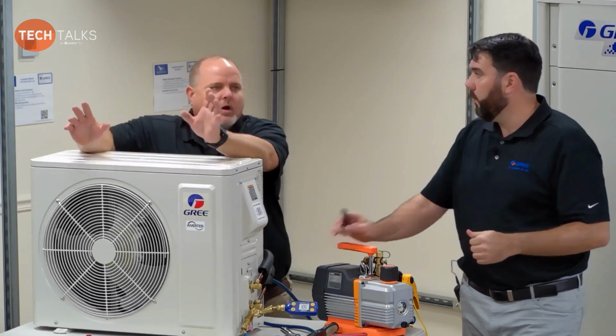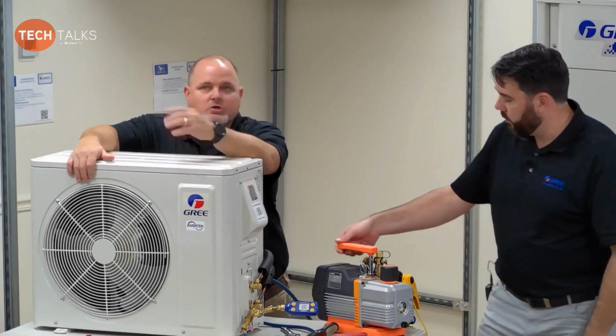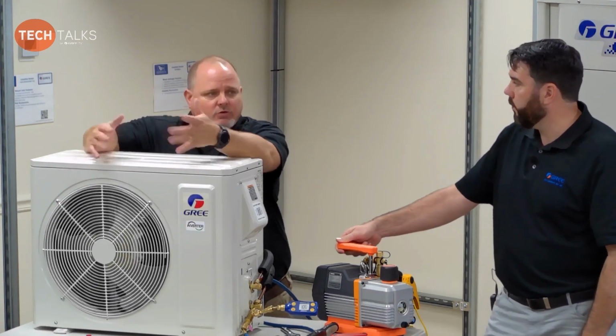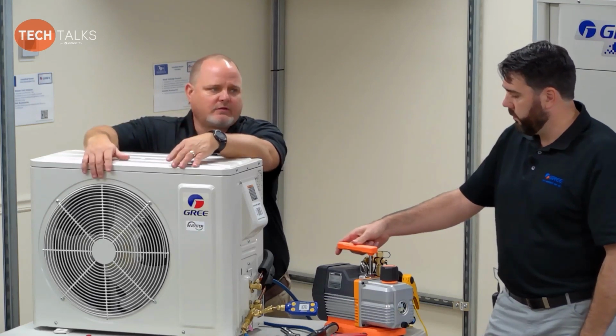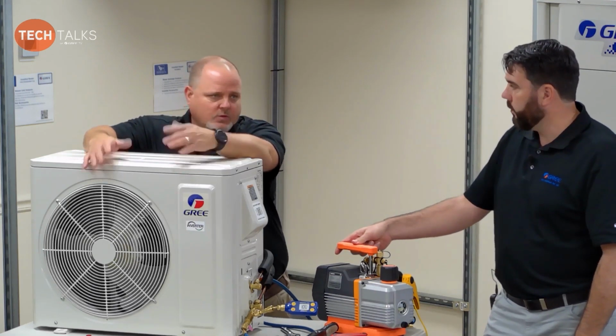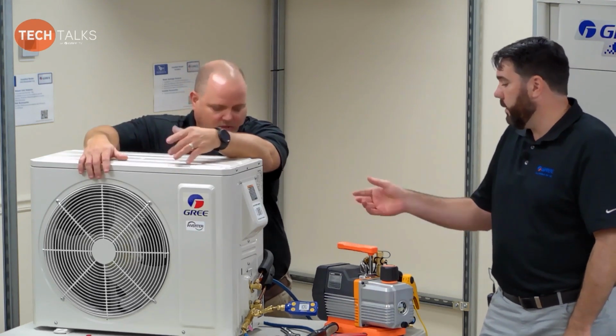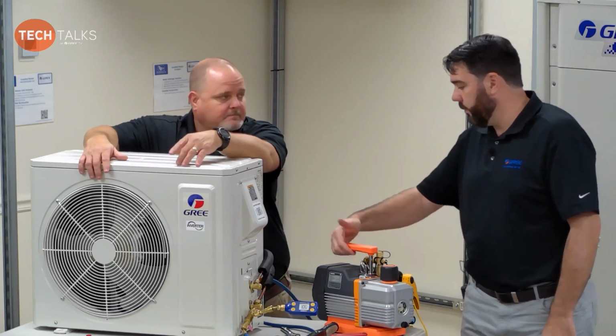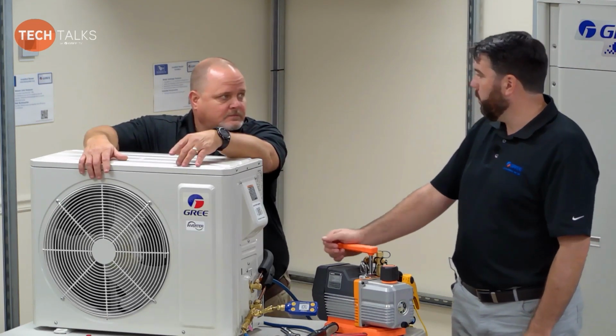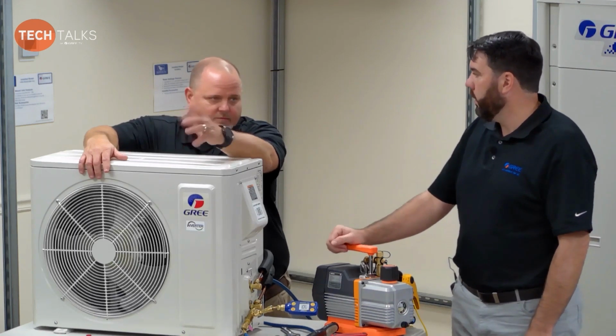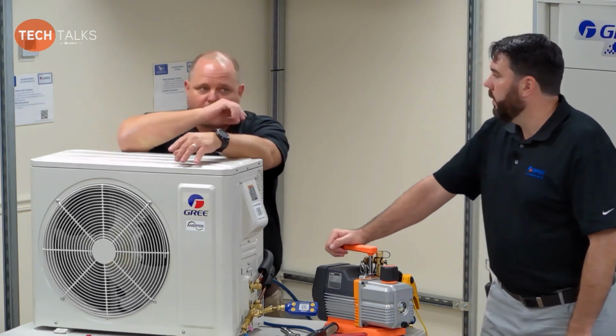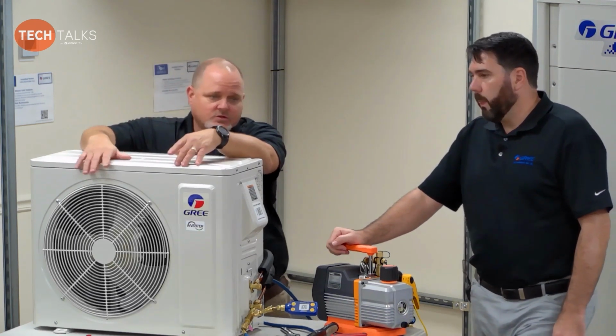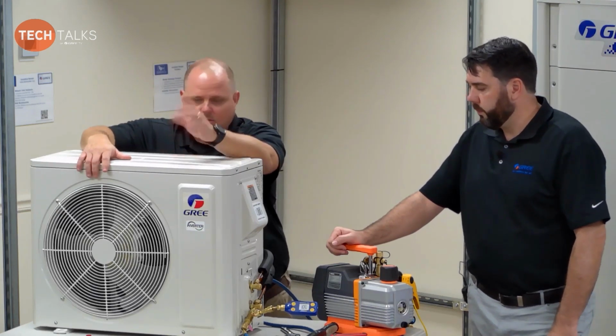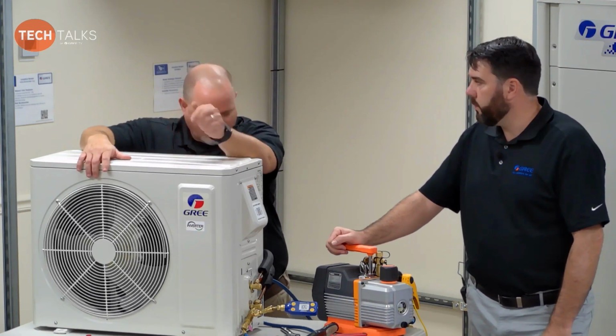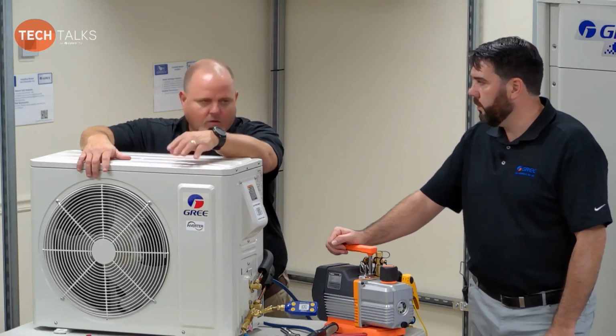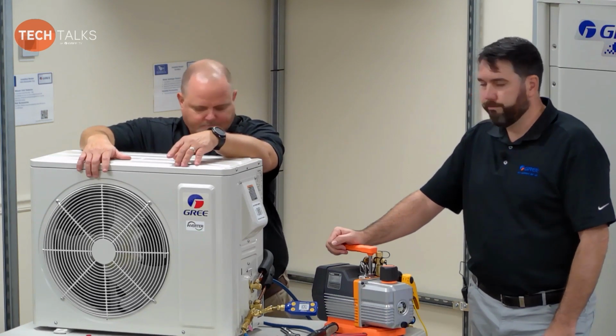Just sharing what we've learned from you guys out in the field, calling in and talking to us. This is what you've run into. And is it possible they're using a little bit too high CFM vacuum pump? I don't know for sure, but I know the flares work. As long as you make the flare properly, use a flare gauge, and torque them to specification, they will work and they won't leak.